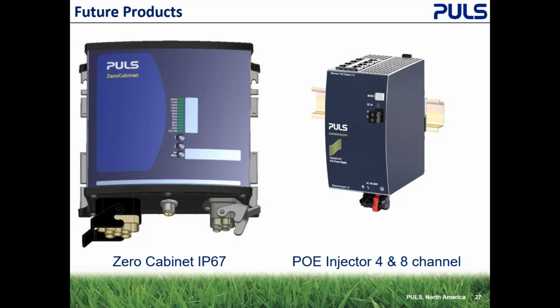To the right, this is an 8-channel PoE injector unit. We'll have 2 - this is the AC in, as you can see on the bottom, neutral and line in, and we'll also have a DC at 48 volts in. So this will put 48 volts out, adjustable up to 56 volts, 8 lines in and 8 lines out. So for cameras, for sensors, you can put them off of this, and this will provide the DC to power the cameras and also pass the data through.